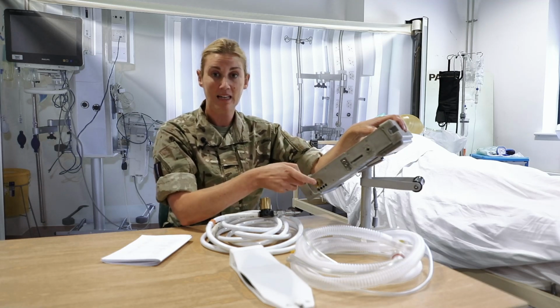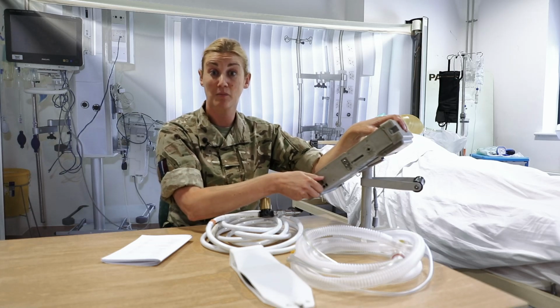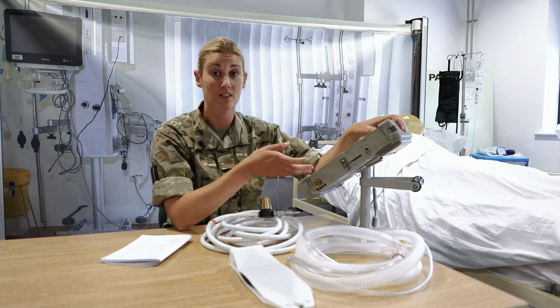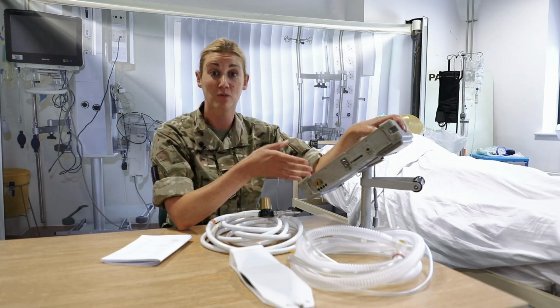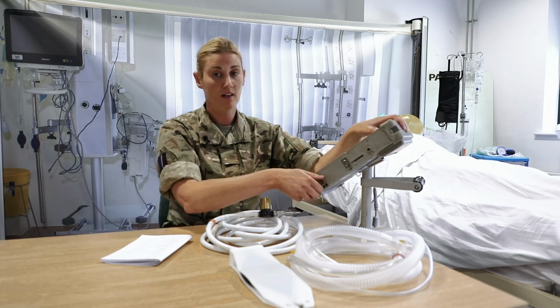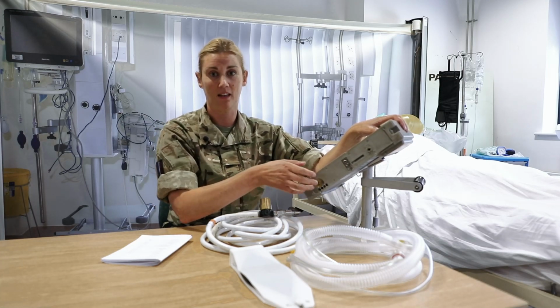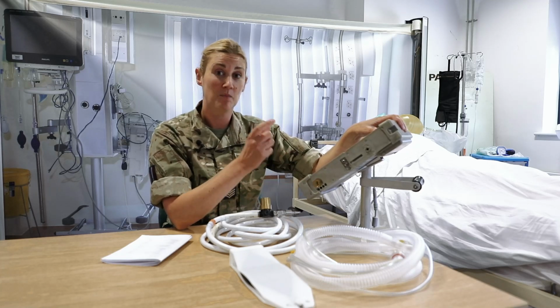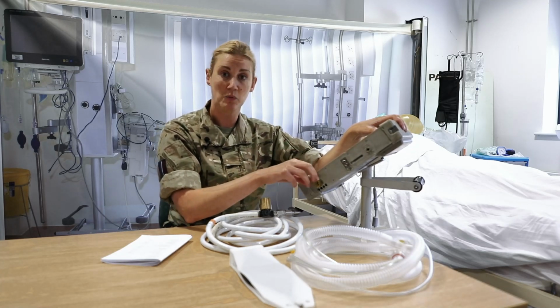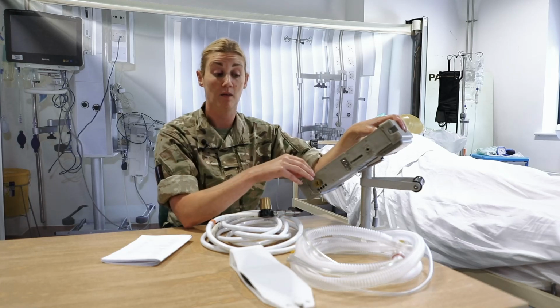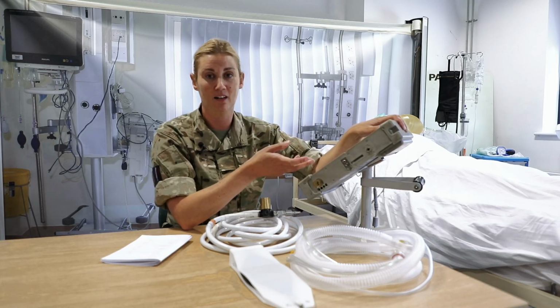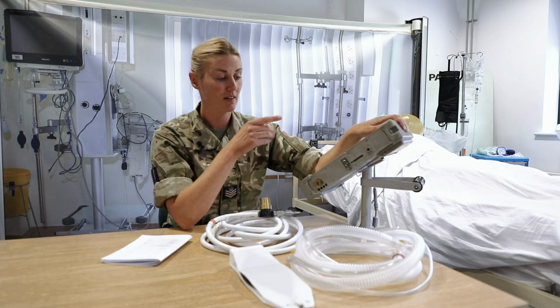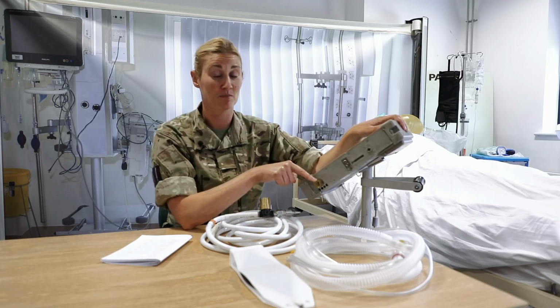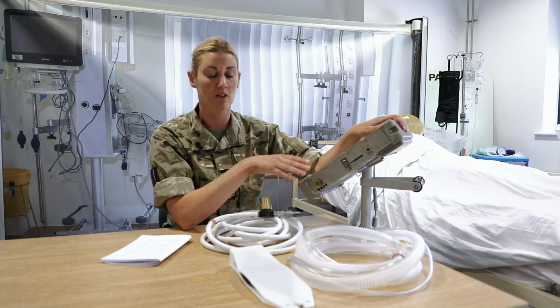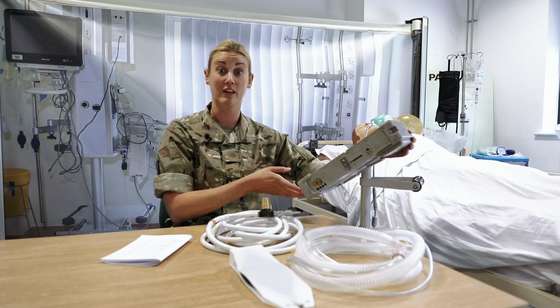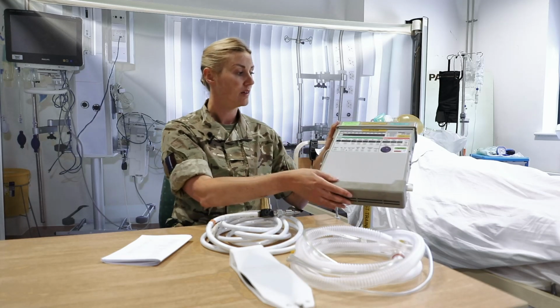You'll notice that this plastic part here is stuck in most machines that you come across. It is actually single patient use and it is found in a new LTV circuit, but most of them have got them stuck in there. What we would advise is, the new circuit that you get, take the 22mm connector out from your bag and place it in a rucksack just in case, because if this falls out randomly, it's really useful to have a replacement, because otherwise you can't connect your ventilator to the patient.